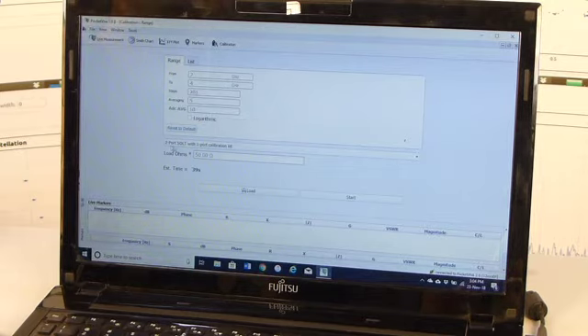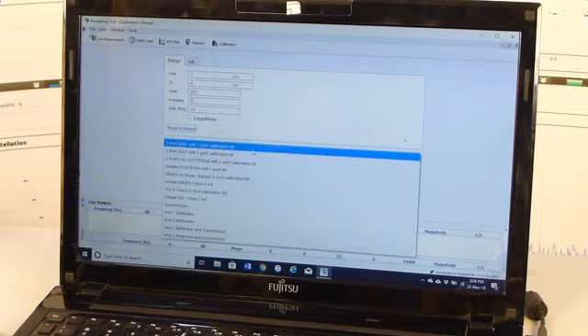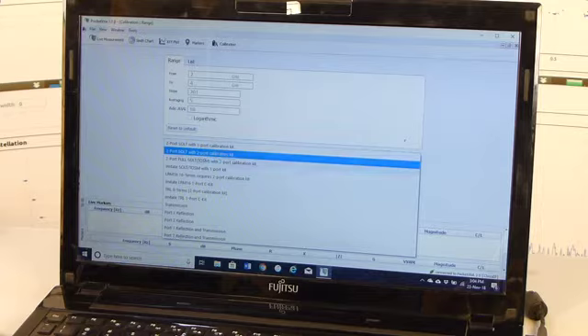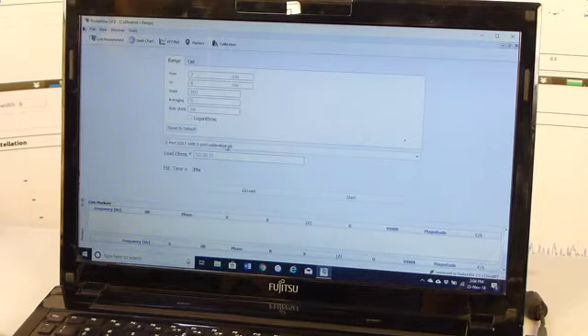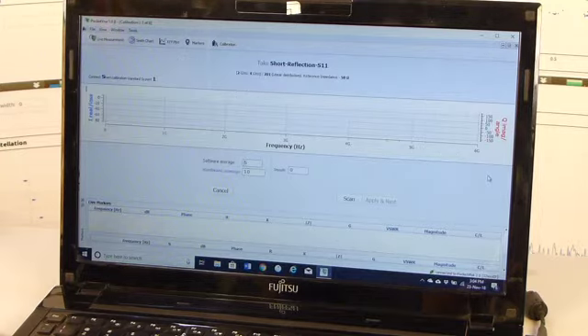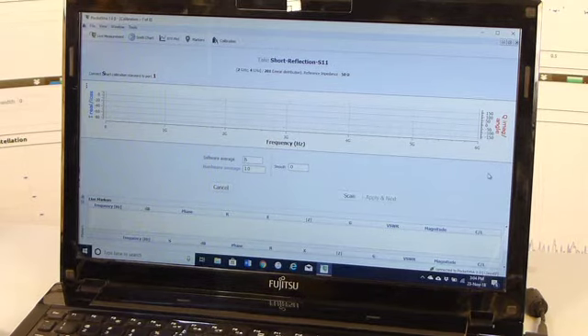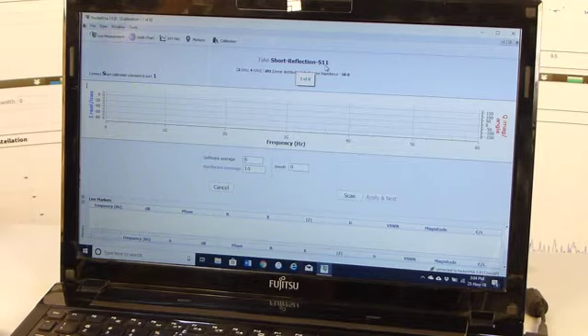And it says 2-port SOLT with 1-port calibration kit. There are different options like SOLT with 2-port and others. Let us select the one which is the default, that is 2-port SOLT with 1-port calibration kit. Now in this we will press start. Now it automatically guides you how to do the calibration of the VNA. For instance, it says take short reflection S11. This port is 1, so S11 will be on this port.